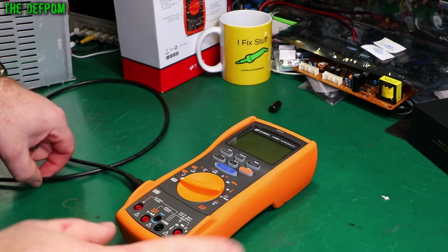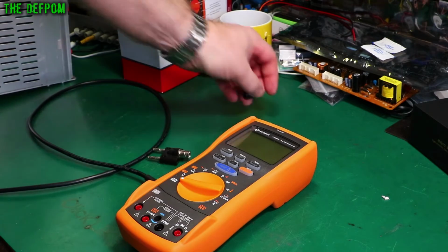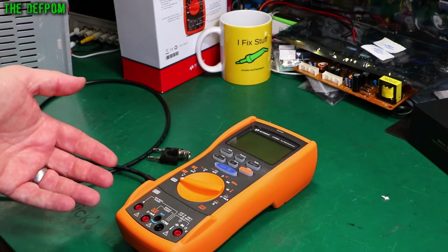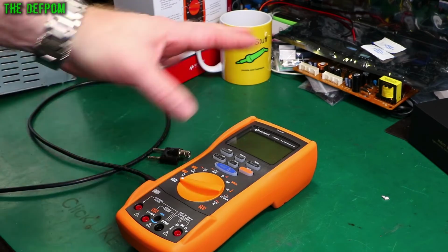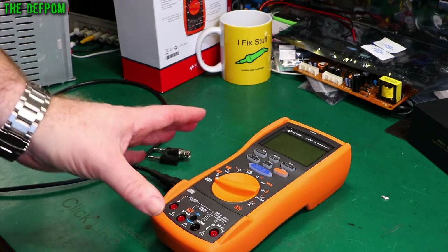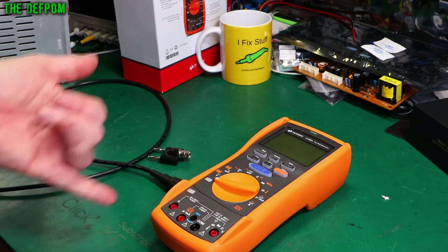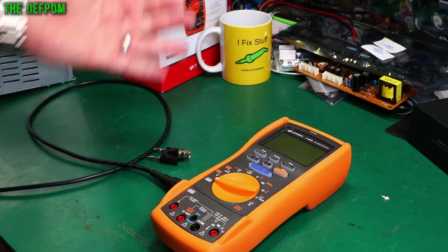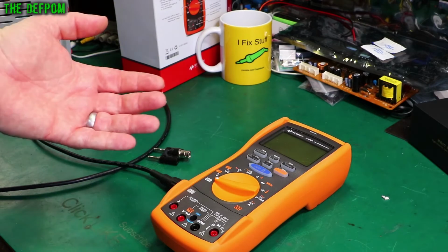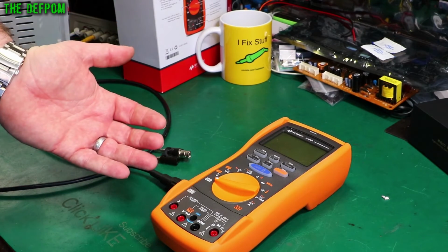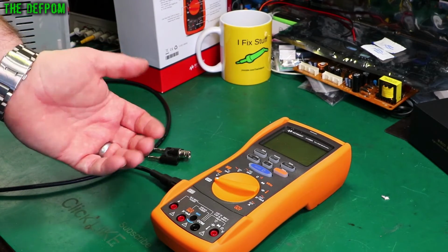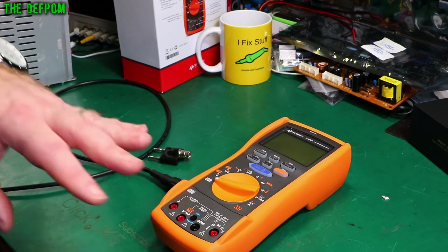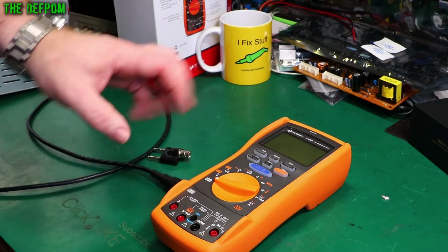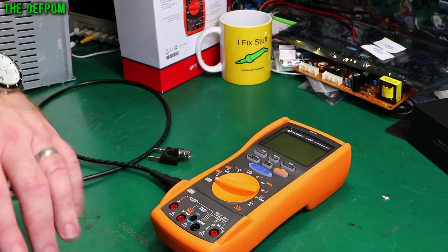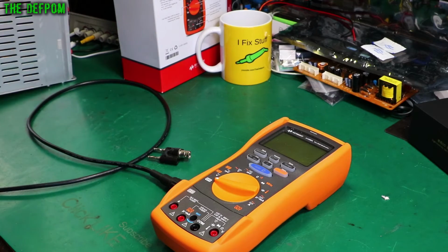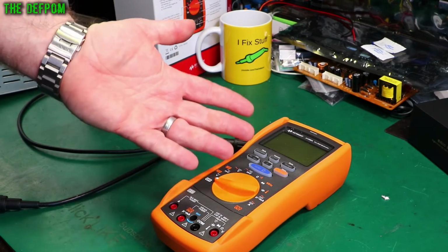But anyway, another interesting point is that when I look at the calibration manual, because you can get the calibration manual for this, it tells you how to do a calibration and verification. The verification points are 1 megahertz and 20 megahertz, as I said before, as on the calibration report. But there's no actual information in the calibration manual on how to calibrate frequency. It's completely absent. There is no mention at all of how to calibrate frequency, which I find very interesting. It tells you how to do everything else. Frequency is not there.